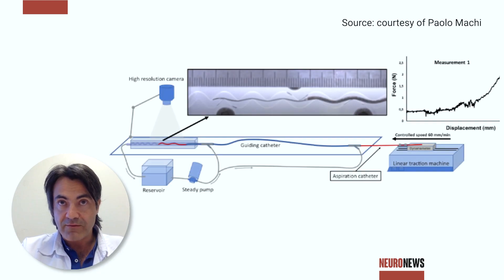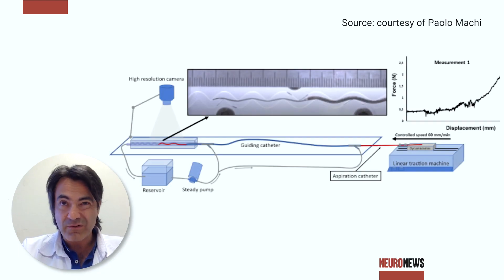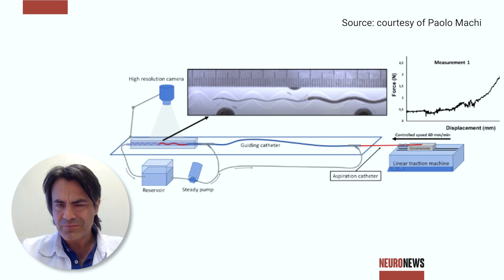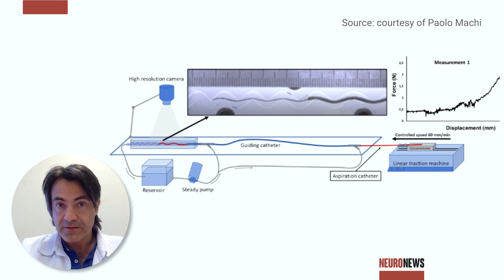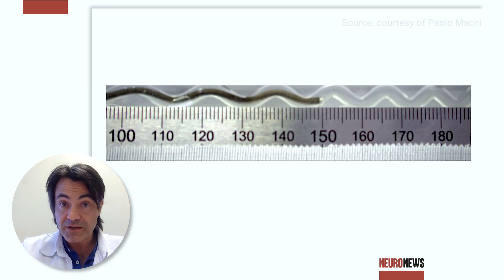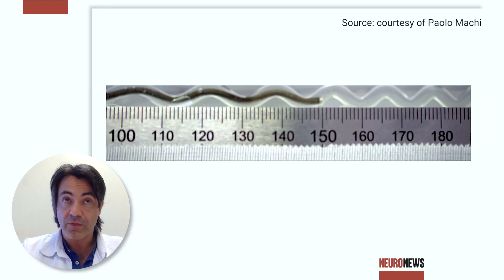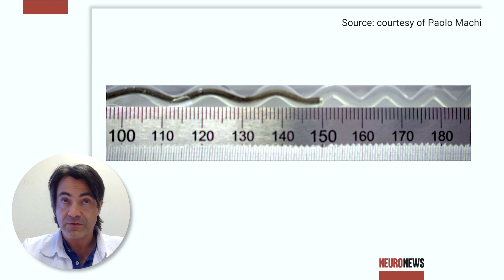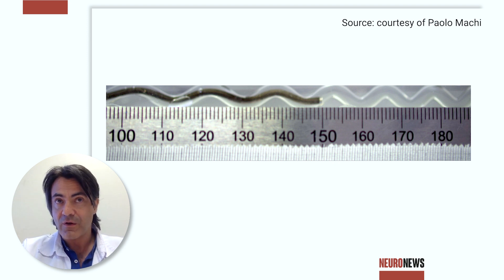Trackability means that we have conceived and developed specific vascular phantoms with specific characteristics, actually challenging the trackability of the aspiration catheters. We use a tensile machine, for example, to push the catheter through the phantoms, measuring the distance covered by the catheter and the force needed to push it through that distance.